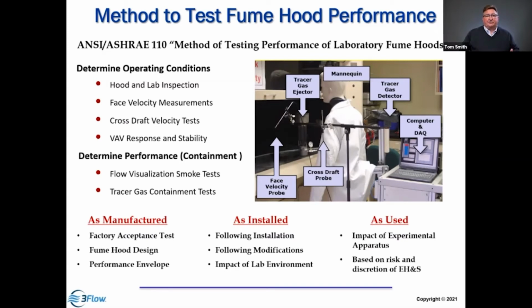So we're going to apply a series of tests. We're going to do our operational test. That's going to inspect the hood in the lab, make sure it's all properly installed and it's equipped appropriately. We're then going to conduct face velocity tests, measure cross drafts, and do a VAV response and stability test. And then, under that set of conditions, we move to the performance tests.